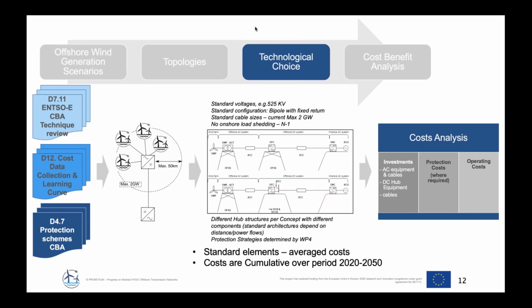Protection costs are currently a percentage of infrastructure cost. This is set at the high end of estimations based on analysis by the Supergrid Institute. The Supergrid Institute made studies on different grid elements resulting from our topology studies. Not surprisingly, they concluded that the best strategy and type of equipment was specific to each grid structure. They considered fully selective, non-selective, and partially selective solutions, utilizing fast circuit breakers and slower mechanical circuit breakers. Also, they concluded that the average cost of protection was between 2 and 9%.